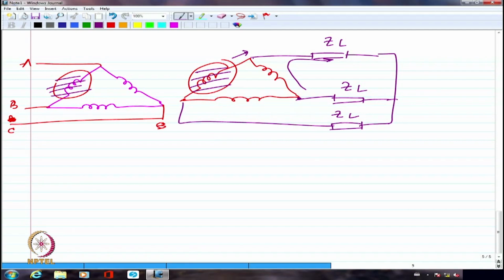I can say if it is delta and star, I am going to have phase voltage and line current, which will give me a phase shift of 30 plus phi or 30 minus phi, like the two wattmeter method. What we did in the case of the two wattmeter method, it will become very similar to that. Because of this, the power factor angle is modified in this open delta connection. I am not planning to go into great detail about open delta connection. All I want you to understand is, if it is delta-delta configuration, although there is no phase shift, and no step up or step down, the one major advantage of delta-delta configuration is that even if one of the transformers conks out, I should be able to operate it at a reduced kVA rating, because it can functionally work properly as a three-phase transformer, despite one of the transformers being opened.